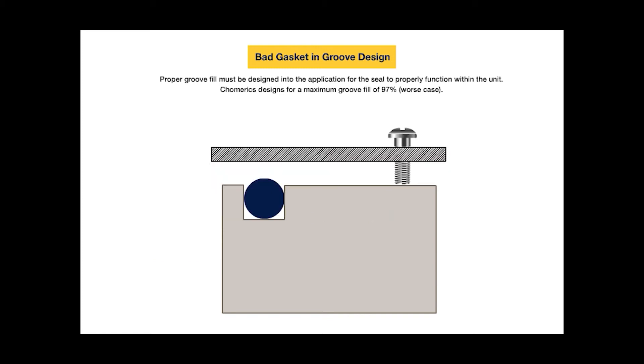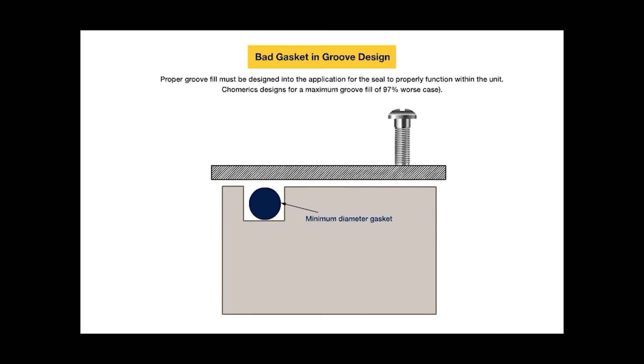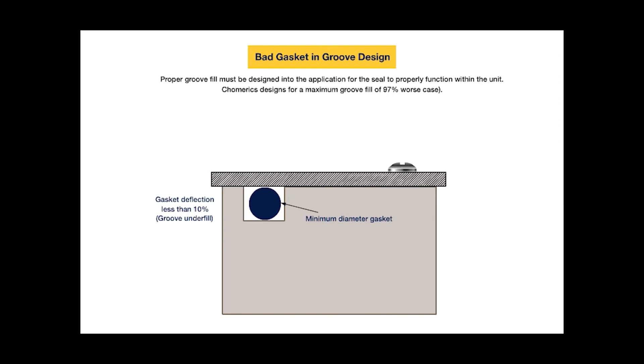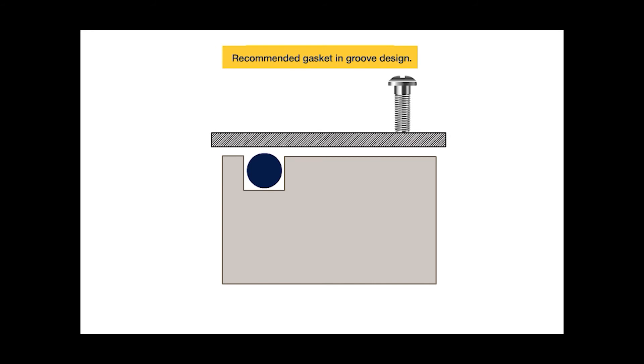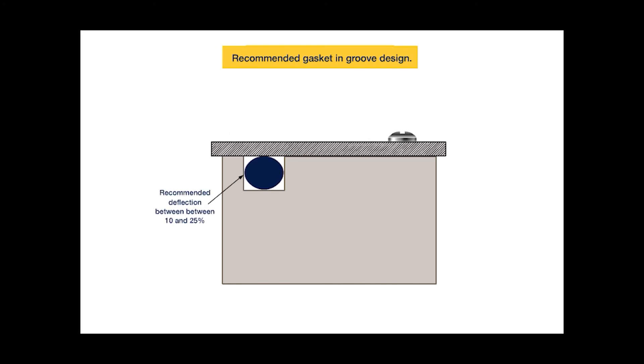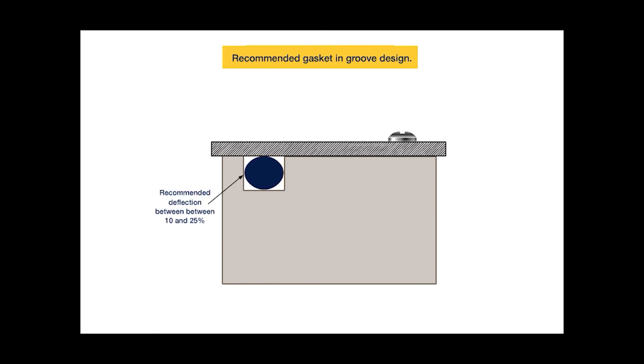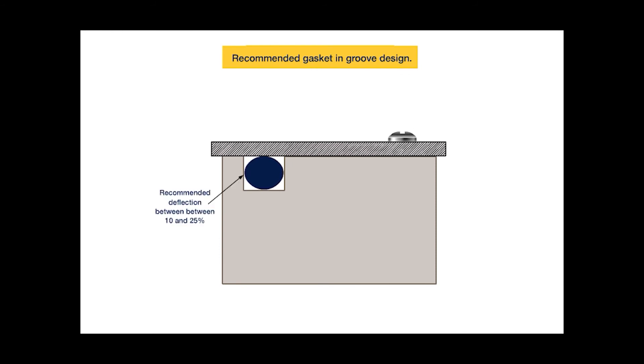This animation shows a gasket that's too small or undersized for the groove — you're getting less than 10% deflection, almost none at all, so you're not getting any electrical contact and effectively no environmental sealing. Finally, we have the 'Goldilocks' gasket — designed properly for the groove with no groove overfill, so the gasket isn't being damaged while still being compressed within the proper deflection range: for a solid-O, between 10 and 25 percent.